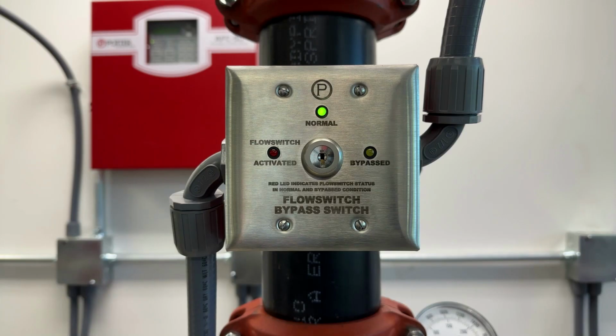Utilizing the Potter Flow Switch Bypass Switch can save you time and headache by removing the need to notify monitoring or response parties as the flow switch is bypassed during maintenance or filling and no alarm signal is sent to the fire alarm control panel.